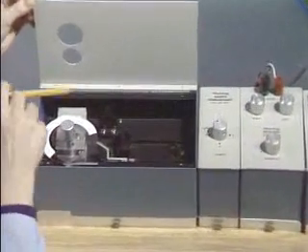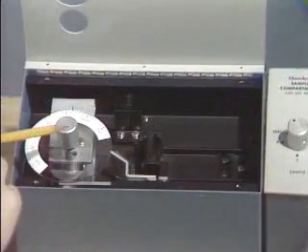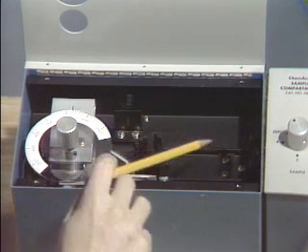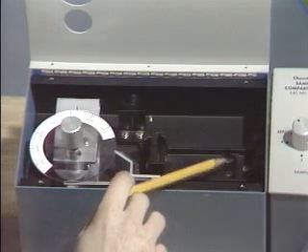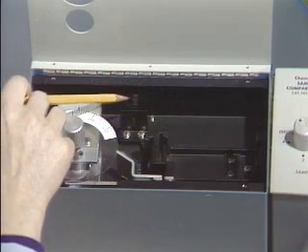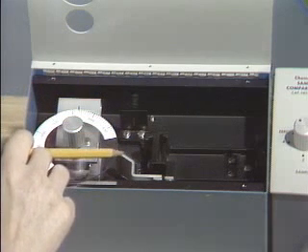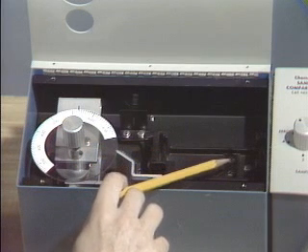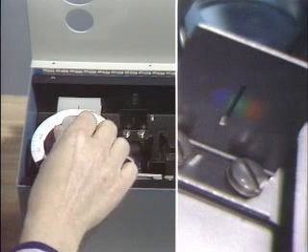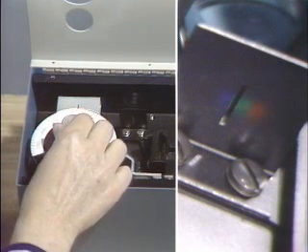The spectrometer consists of a light source, a wavelength control knob, a prism or grating, and a slit. In this case, the light source is a bulb which provides white light. The light is focused onto a mirror and then reflected onto the grating. The grating disperses the light into a spectrum of colors. By turning the wavelength control, the angle of the mirror is changed and the position of the spectrum that falls on the slit is moved. The narrowness of the slit allows only a small portion of the spectrum to pass through the solution in the cell on the other side of the slit.